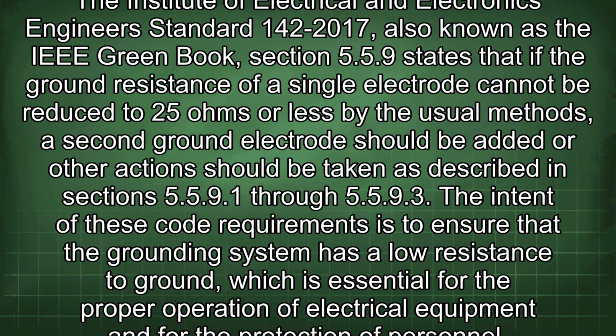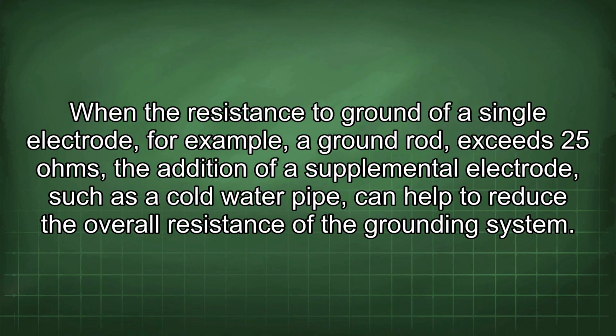The intent of these code requirements is to ensure that the grounding system has a low resistance to ground, which is essential for the proper operation of electrical equipment and for the protection of personnel. When the resistance to ground of a single electrode, for example a ground rod, exceeds 25 ohms, the addition of a supplemental electrode, such as a cold water pipe, can help to reduce the overall resistance of the grounding system.